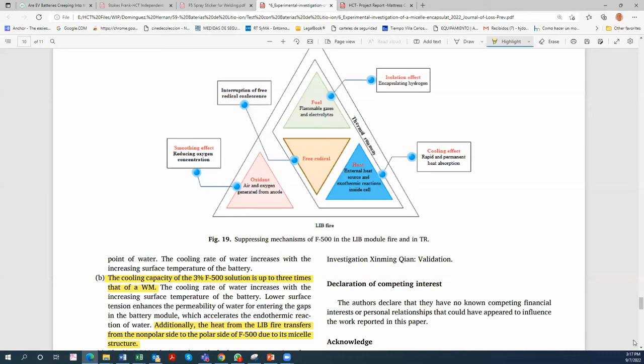What's highlighted here: the sentence before says that the F500 reduces surface tension, allowing droplets to permeate into gaps in the battery. However, the thermal reduction of energy is a result of the micelle structure, not simply a result of reducing surface tension and letting water spread across the battery into crevices. The heat reduction is a function of the spherical micelles, which is what we were talking about.